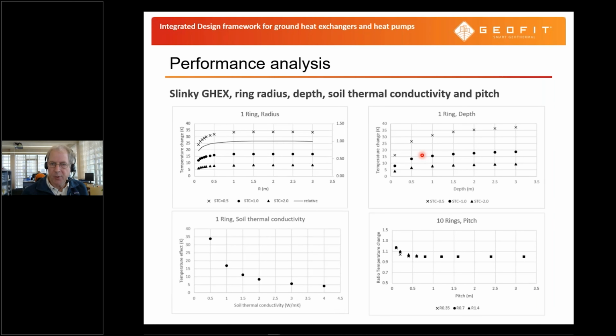Then we started looking at other parameters, such as the radius of a ring, where we can have, for different soil conductivities, we can calculate what the effect is if the ring diameter or the radius of the ring increases. And we can see that there is a kind of cutoff where, if the ring radius is above a certain value, let's say between 0.5 and 1 meter, there is no additional effect of the ring radius. So we can say that there is a kind of minimum ring radius that is required to make sure that the radius itself is not negatively affecting our performance.